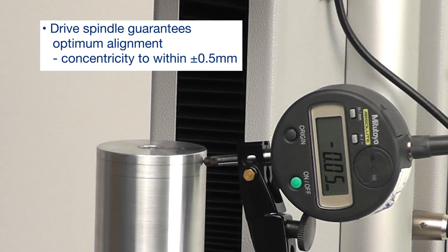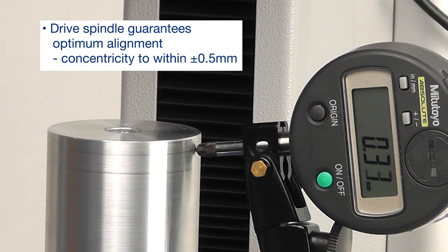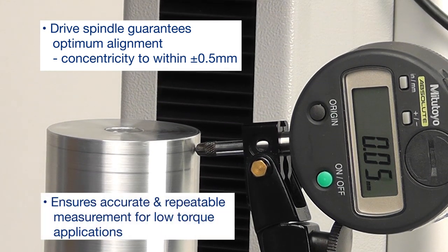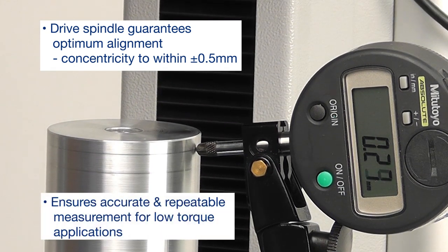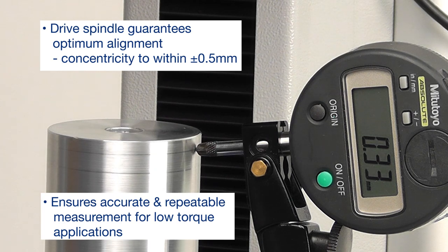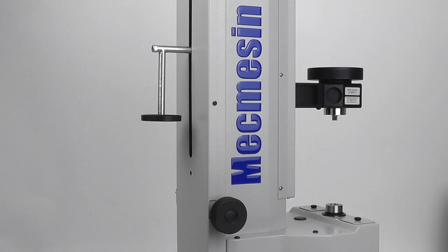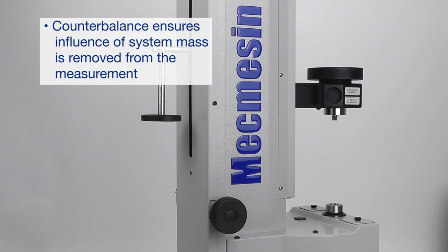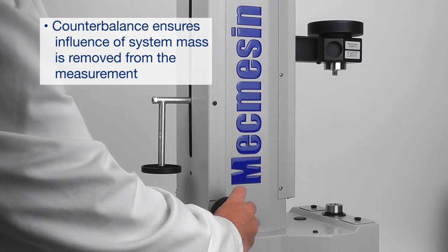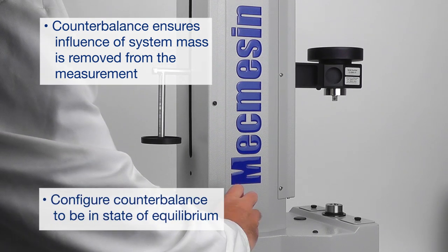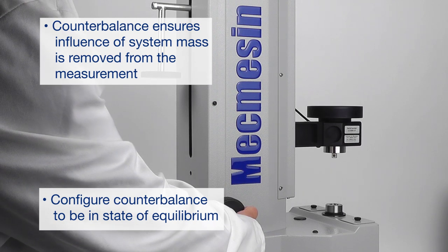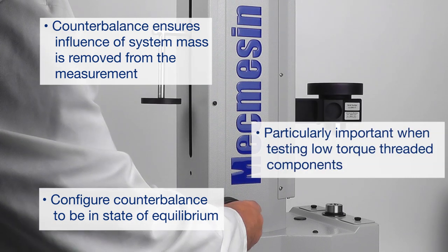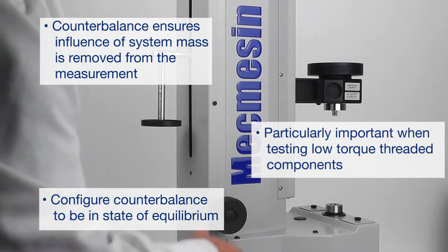The drive spindle is aligned to within half a millimeter, which ensures low torque measurements can be made accurately and repeatedly. A counterbalance system removes the influence of the system mass from the measurement, which is particularly important when testing low-torque threaded components.